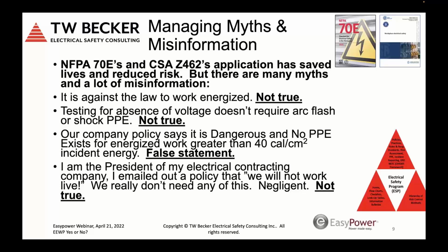Testing for absence of voltage doesn't require arc flash and shock PPE. That's not true. Until you establish zero volts with an approved test instrument, you're going to need to complete an arc flash and shock risk assessment to determine additional protective measures required. The third one is another myth. It's dangerous, there's no PPE for energized work greater than 40 calories. That's a false statement. Arc blast pressure doesn't correlate to incident energy, as defined by Dr. Ralph Lee's research and a graph that's published in the old IEEE Yellow Book, which is now the new IEEE 3007 series, right? So that's another sort of myth.